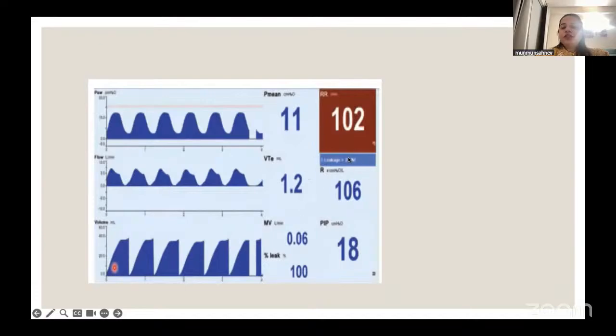The parameters expressed on the screen show us a rate of 102. A baby would normally breathe at around 60, and this is breathing at 102. So it gives me an idea that there is some sort of auto-triggering happening. Again, the tidal volumes are not being met. The resistance is high. As the tidal volumes are not met, the minute ventilation also seems to be a little low, and we see 100% leak.